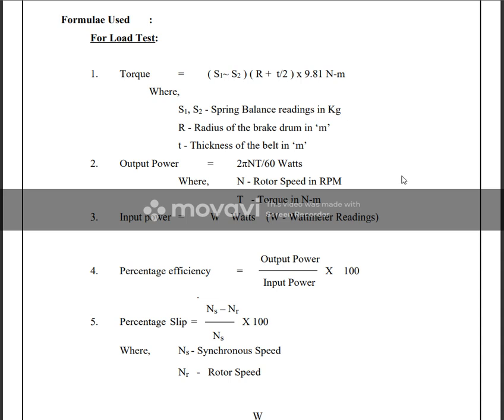Formulas for load test: Torque is equal to (S1 minus S2) multiplied by (R plus T over 2) multiplied by 9.81 Newton meters, where S1 and S2 are spring balance readings in kg, R is the radius of the brake drum in meters, and T is the thickness of the belt in meters. Output power can be calculated as 2πNT divided by 60 Watts, where N is the rotor speed in RPM and T is the torque in Newton meters.